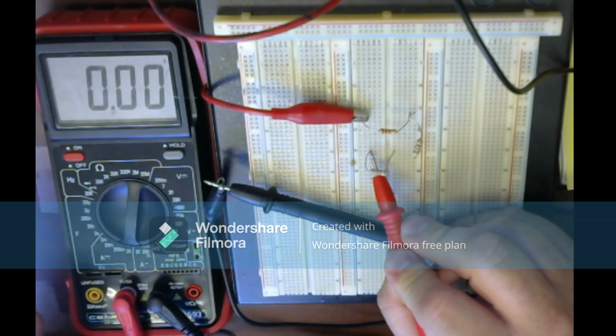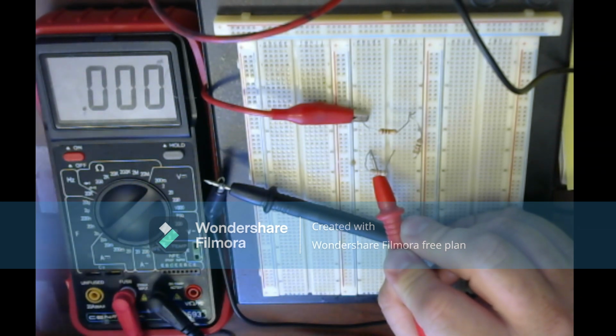Now I'm going to look down at my dial. I was calculating for 1.683 milliamps, so I can turn that to my smallest setting, which is 2 milliamps. I've got 2, 20, and 200 milliamps settings. We're going for the 2 because that's bigger than what I'm expecting. And if we were worried, or really close to the line, we could bump it up one level to be safe.